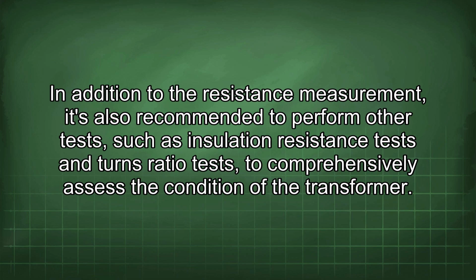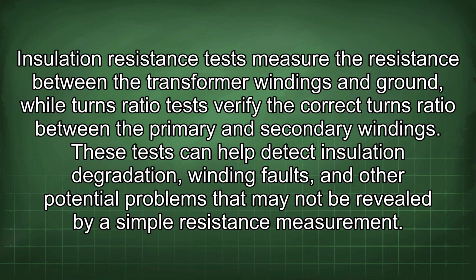This information can be used to verify the accuracy of the calculated resistance and to identify any potential problems. In addition to the resistance measurement, it's also recommended to perform other tests, such as insulation resistance tests and turns ratio tests, to comprehensively assess the condition of the transformer. Insulation resistance tests measure the resistance between the transformer windings and ground, while turns ratio tests verify the correct turns ratio between the primary and secondary windings.